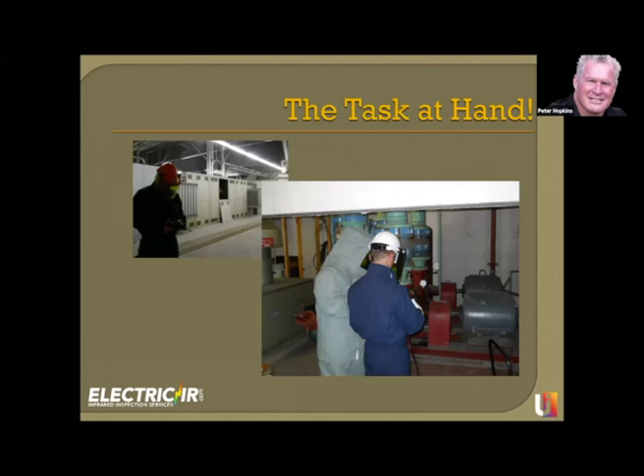There are a number of other things that are part of it. Typically, anything receiving electricity is what's going to be seen, like motors. Just a tip, with motors, what you're looking at is called trending. Motors are difficult to assess unless you know the standard criteria for that existing motor, like its maximum temperature. So what you're doing is running a weekly, monthly, or quarterly test on every motor and then trending it. It's the main bearing you're watching, and as that temperature rises, we can predict the failure.